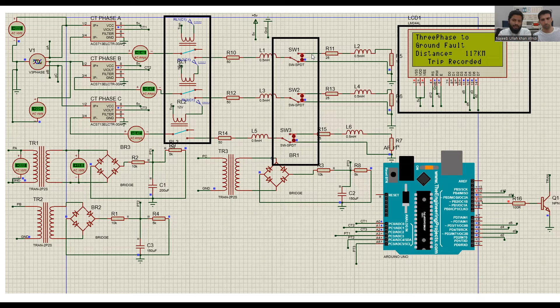So we have modified our Proteus model in order to give the fault at a different location, to check the reliability of the distance relay, that it is actually giving us the accurate result of the distance or not. So we have modified our Proteus model. The line distance is 150 and with a total impedance of 30.18 ohms. And as we can see here, there are different switches used to add fault in the transmission line. This is the normal operating condition.